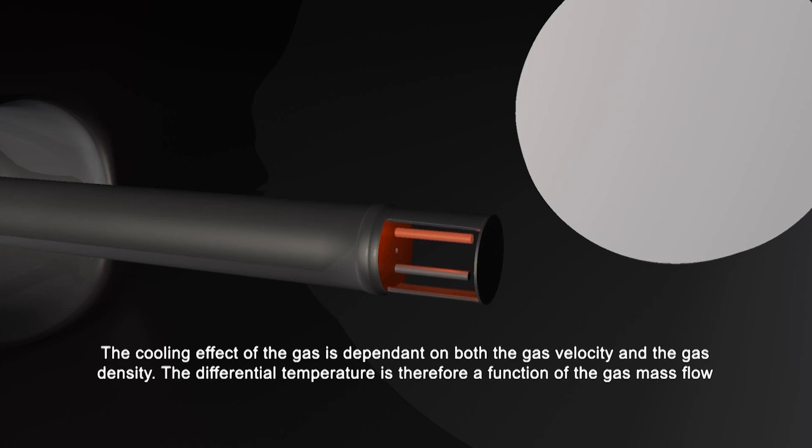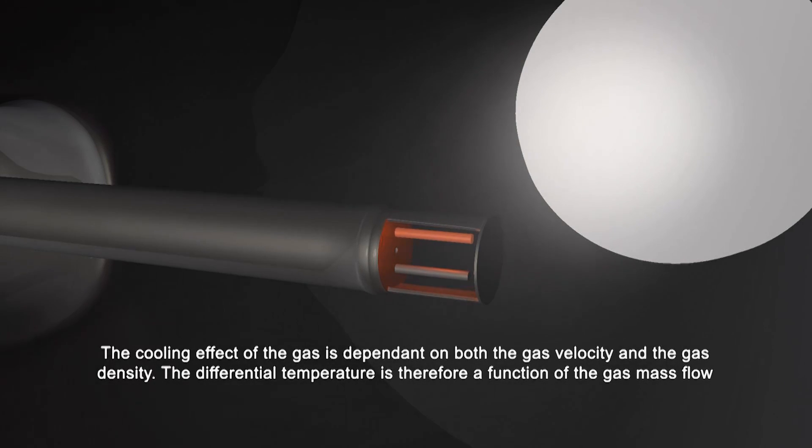The cooling effect of the gas is dependent on both the gas velocity and the gas density. The differential temperature is therefore a function of the gas mass flow. The temperature of the gas is also monitored and used in the mass flow equation.